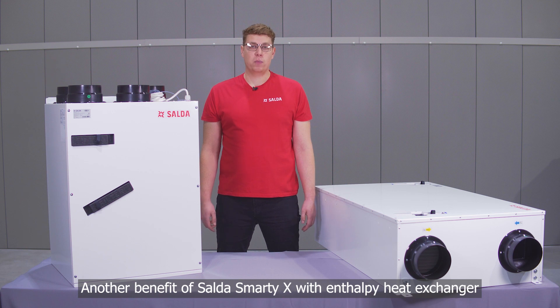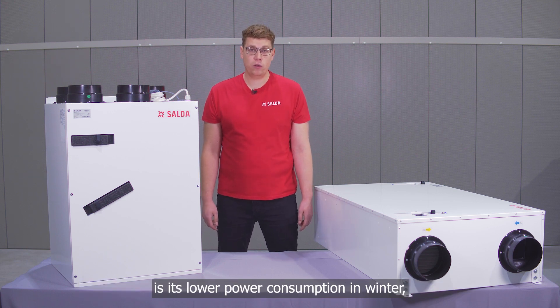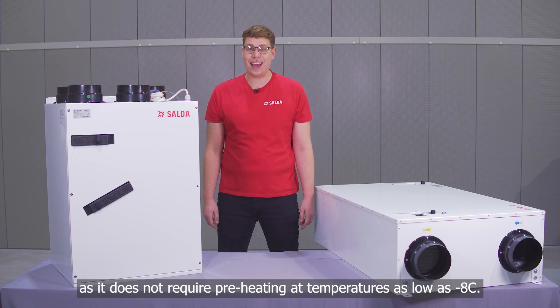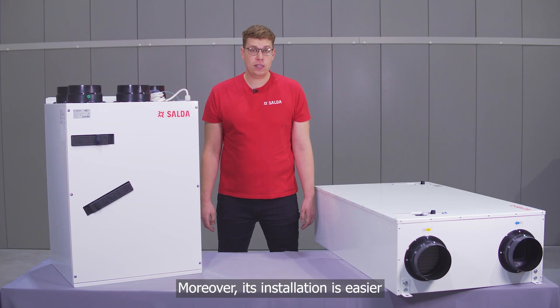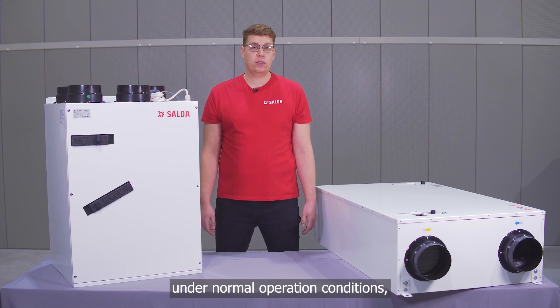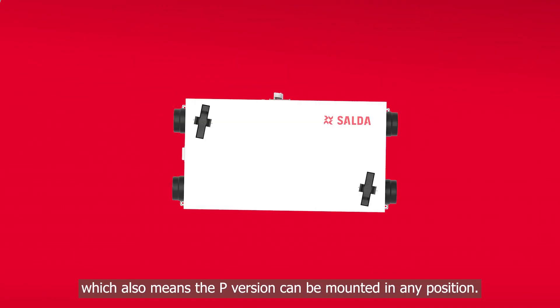Another benefit of the Salda Smarty X with Enthalpy heat exchanger is lower power consumption in winter, as it does not require preheating at temperatures as low as minus eight degrees Celsius. Moreover, its installation is easier as it does not require a condensate drain under normal operating conditions, which also means the P version can be mounted in any position.